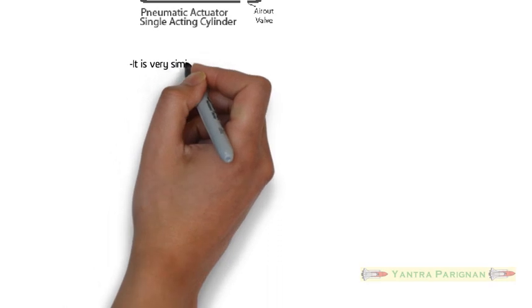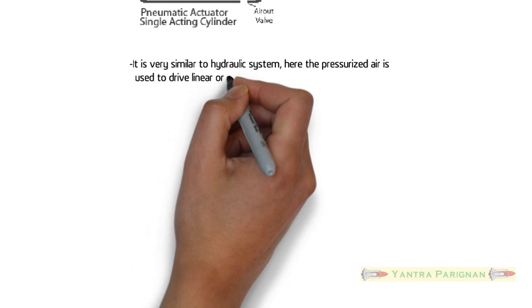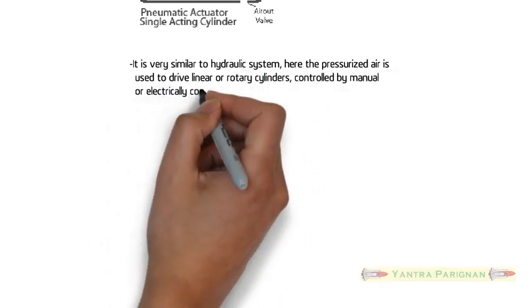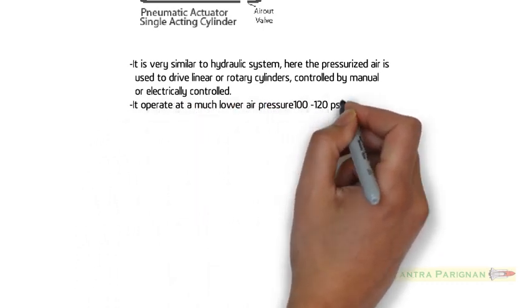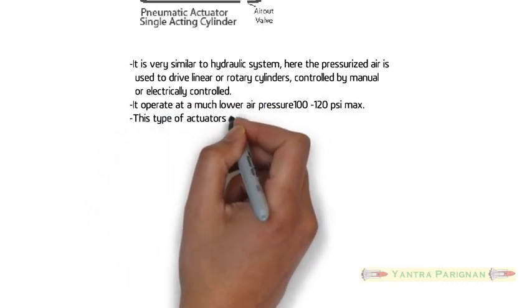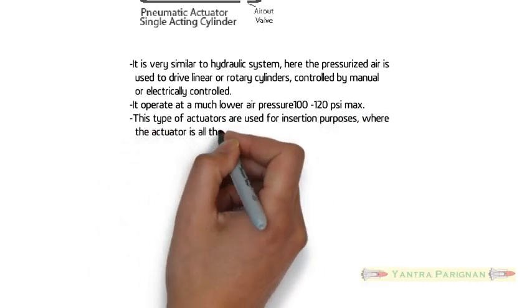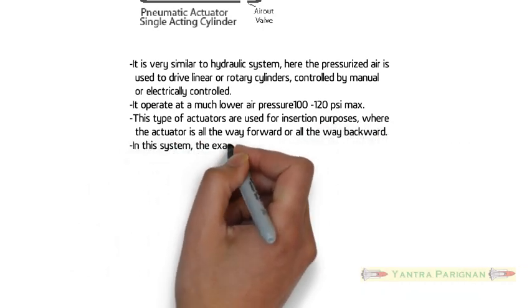It is very similar to hydraulic systems. Here the pressurized air is used to drive linear or rotary cylinders, controlled by manual or electrically controlled valves. It operates at a much lower air pressure, 100 to 120 pound force per square inch maximum. This type of actuator is used for insertion purposes where the actuator is all the way forward or all the way backward.